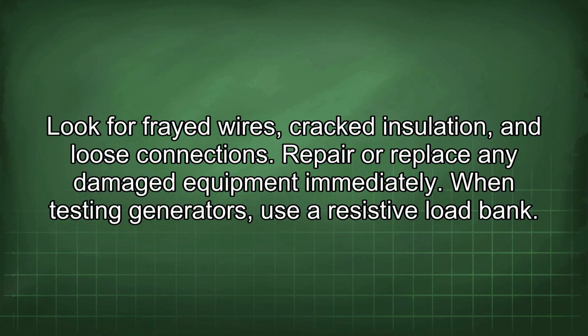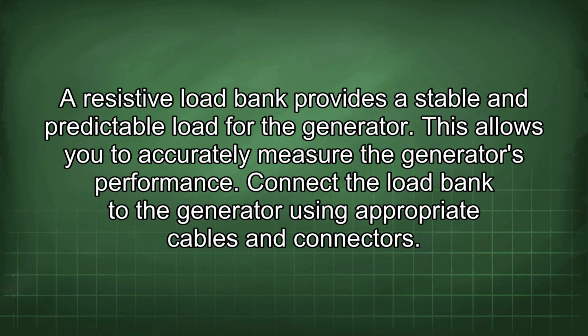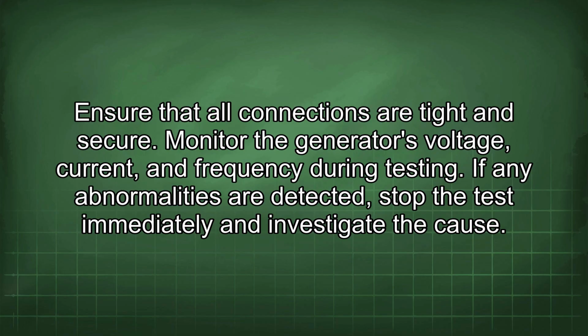When testing generators, use a resistive load bank. A resistive load bank provides a stable and predictable load for the generator. This allows you to accurately measure the generator's performance. Connect the load bank to the generator using appropriate cables and connectors. Ensure that all connections are tight and secure. Monitor the generator's voltage, current, and frequency during testing. If any abnormalities are detected, stop the test immediately and investigate the cause.